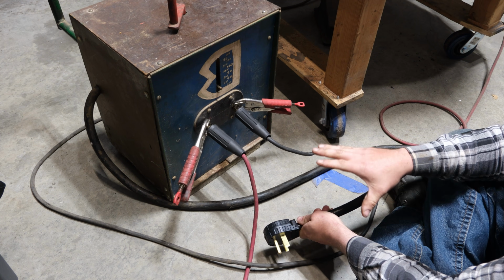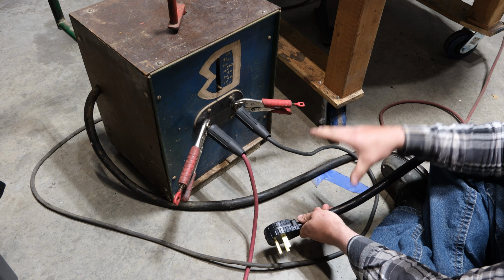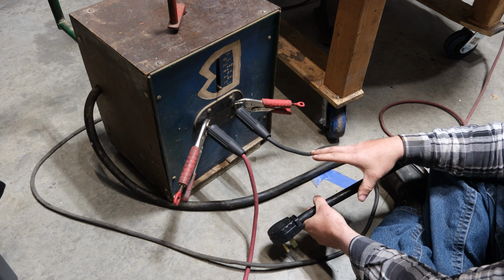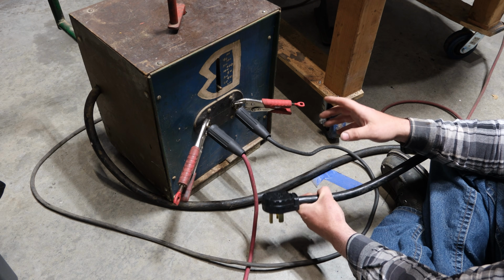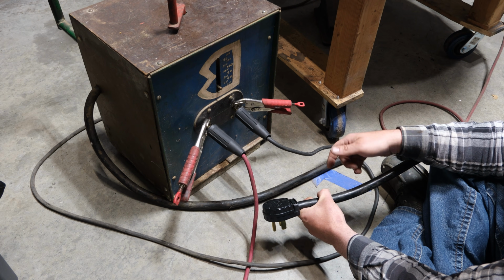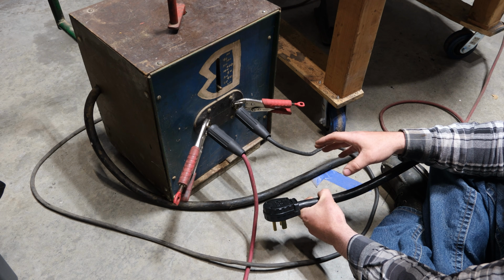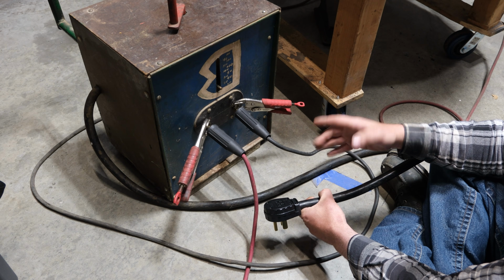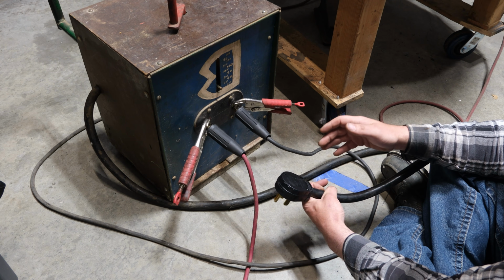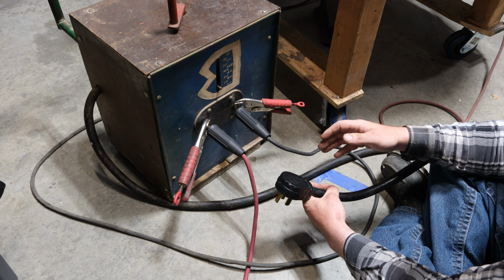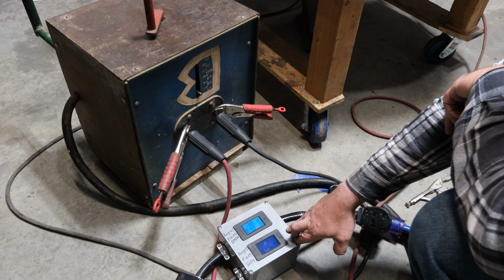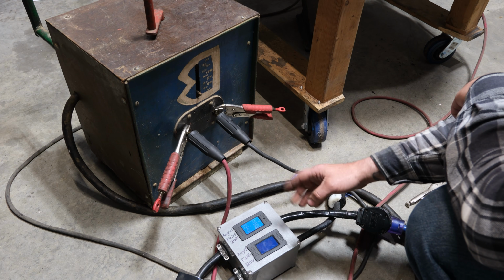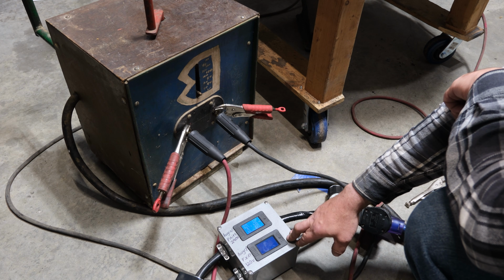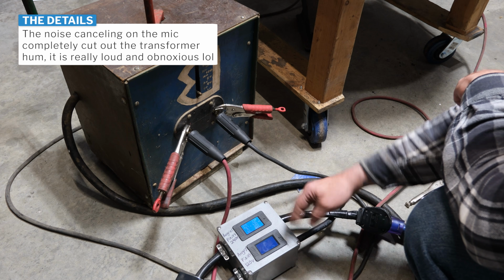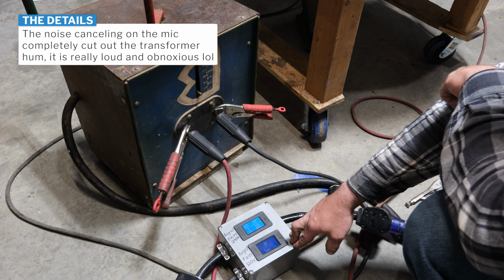So anyways, now that this thing's kind of set up, what I'm going to do is plug it in, well, plug it in with the breaker off so I'm nowhere near this, flip the switch and make sure that the breaker holds. I have it on almost the lowest it'll go, and I guess we'll see what happens. Well, this sucker's got quite a little rattle to it. The laminations in that transformer probably aren't tight anymore, and it has a little bit of shimmy in it due to all the angry pixies rolling around in it.